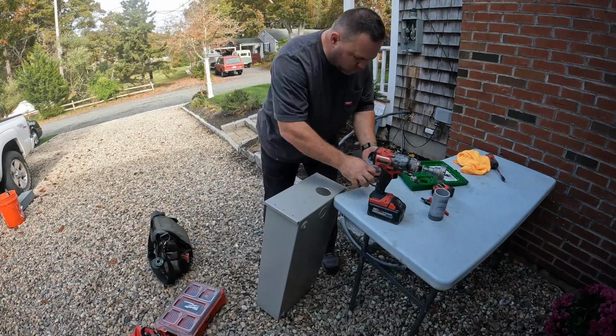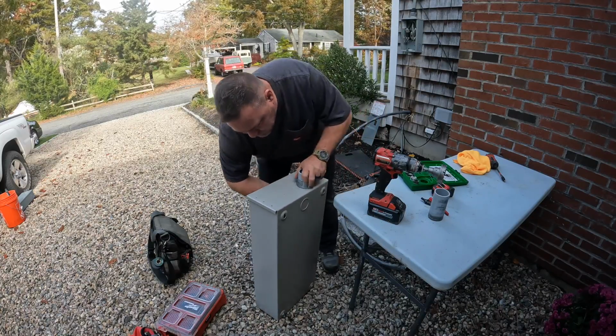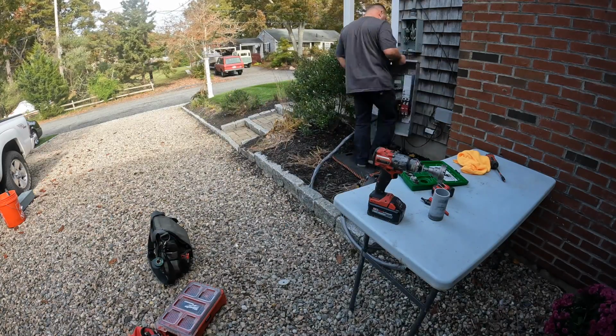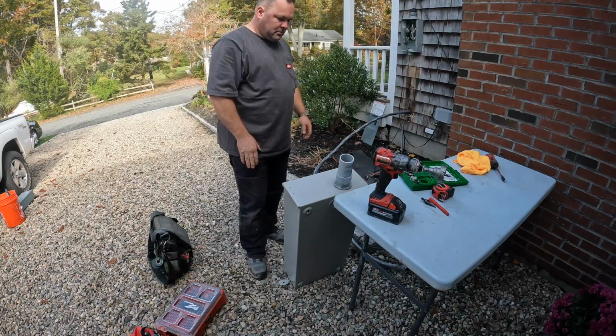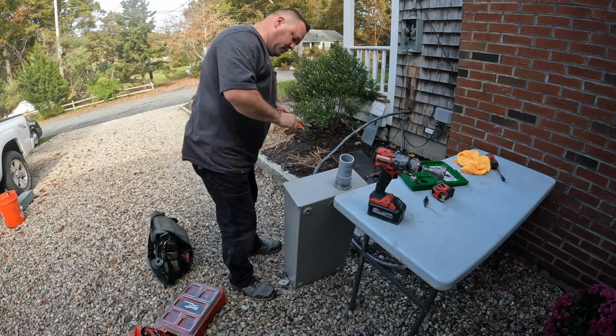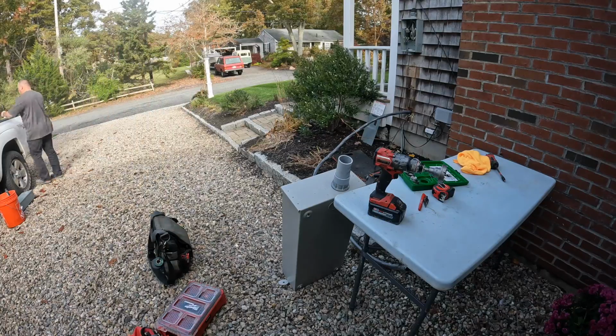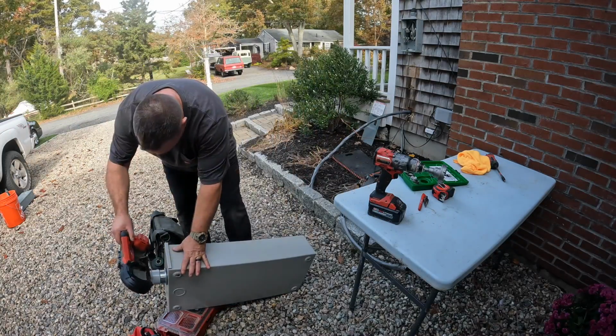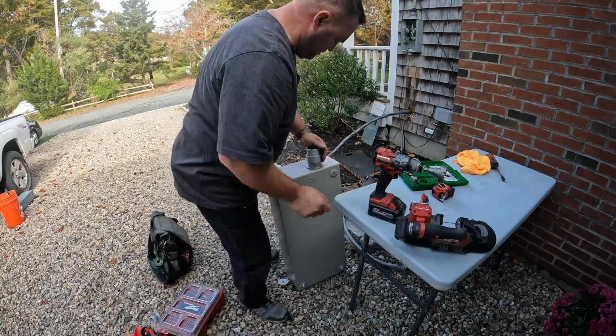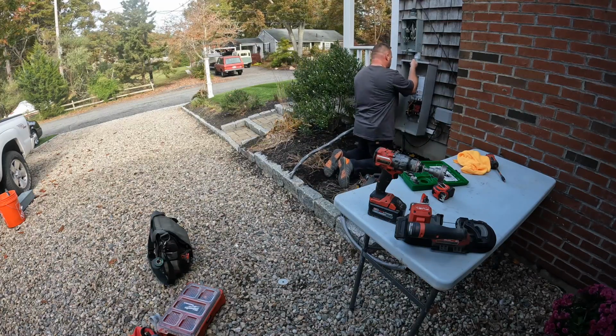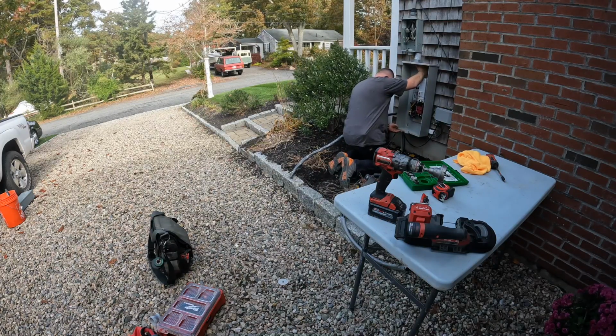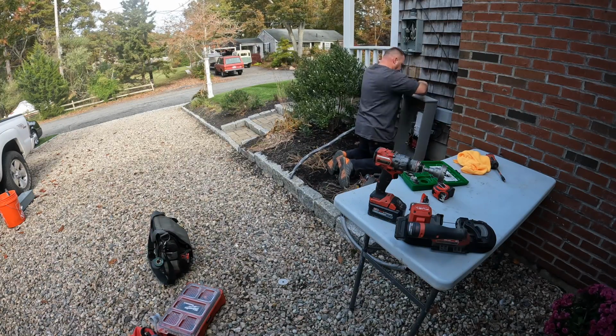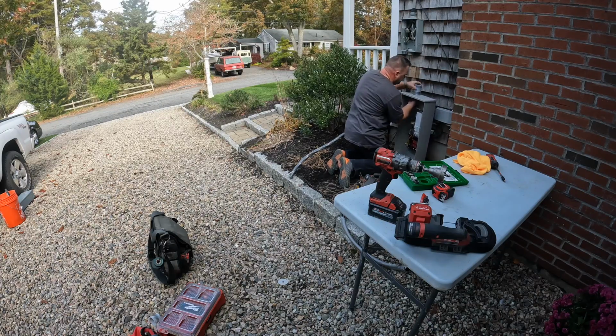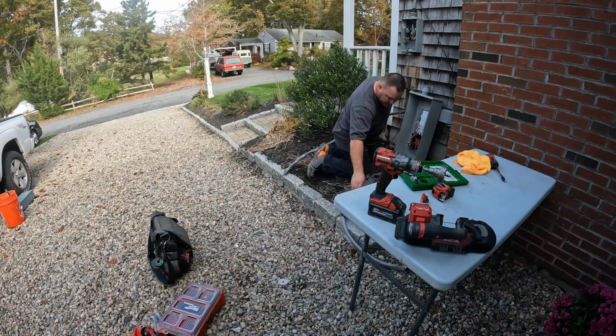I never knew the greatness of the Myers hubs until recently. And so what I used here was a 2-inch male adapter coming out of the bottom of the meter, and just a little small filler piece between the 2 male adapters. And then, of course, the male adapter that ties into the Myers hub at the top of the transfer switch here. And the Myers hub is a preventative measure to keep water out of the transfer switch. So that's why I used it.